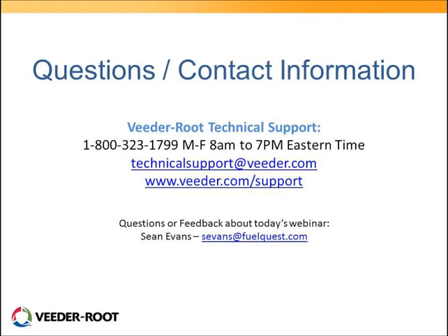Okay, so the requirement is going to be that on an annual basis you will have to have a certified individual who's been certified on, we'll say, Veeder-Root equipment to come out and perform an annual certification on the tank gauge, and then more importantly they will have to verify that the interstitial sensors are operable, that they go into alarm when tripped. And you'll have to do that for any sensor that's installed at the site.